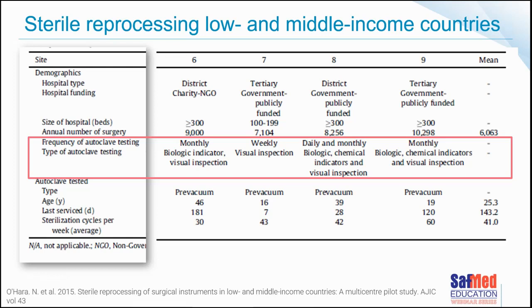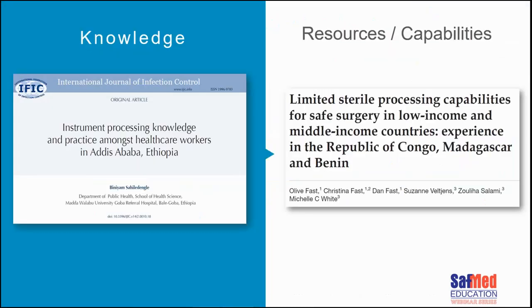For hospitals six through nine, testing frequency was similarly varied — monthly, weekly, daily, monthly. Some used visual inspection, and I'm not sure if that meant looking at the printout or looking at the packs themselves. If you want to ensure that your devices are safe to use on patients before they leave your department, you need trained and knowledgeable staff and the right resources — including equipment and consumables to monitor and validate sterilization processes.